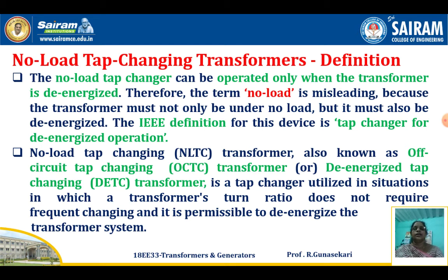Now we study the definition of no load tap changing transformers. The no load tap changer can be operated only when the transformer is de-energized. That means the term no load is misleading, because the transformer must not only be under no load condition but must also be de-energized. Therefore, the IEEE definition for no load tap changing is the tap changer for de-energized operation.